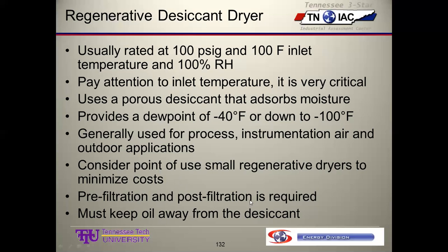Pre and post filtration is required. It's easy to foul this desiccant, and if you get a bunch of crud in those pores on the desiccant, a lot of times you can't get it out, and then you just have to replace it. Replacing desiccant is fairly expensive, so you'd like to only do that at the standard interval, about every 5 years. But for example, this desiccant loves oil. So if we have a lube injected compressor, we really want to try to filter out any oil at all before the dryer to protect our desiccant, or we're going to wind up replacing it much more frequently at some fairly significant cost. So that's what it's saying here.